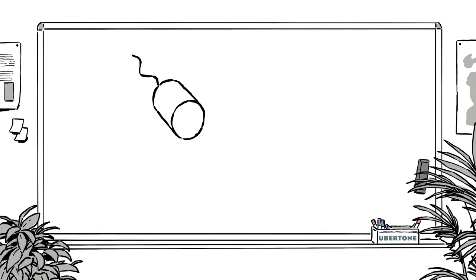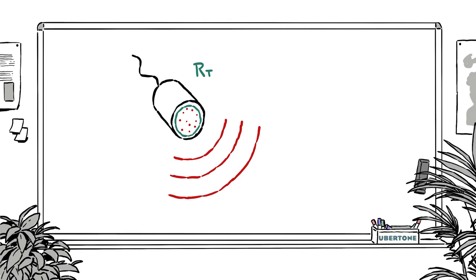The transducer converts the electrical signal generated by the hardware into an acoustic wave. When vibrating, the active surface of the transducer is comparable to a lot of small elements vibrating, resulting in a diffractive phenomenon and in a spherical wave. The active surface is characterized by its radius. The beam shape can thus be represented by the following model of the Rayleigh integral.